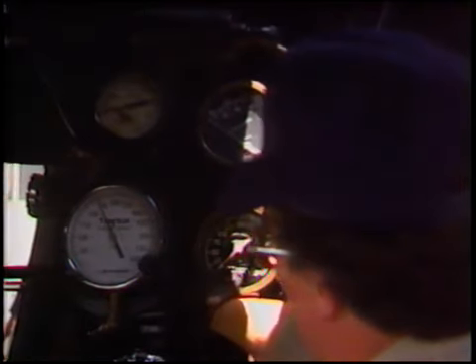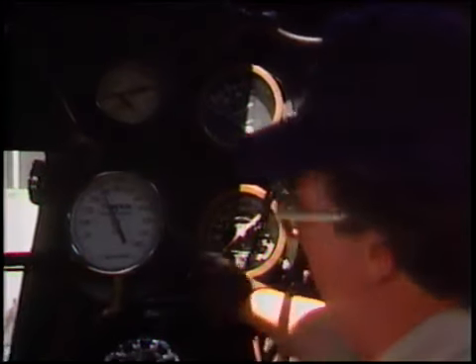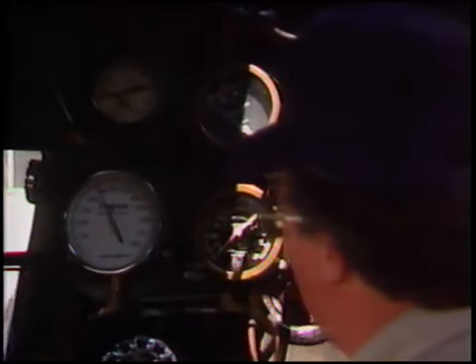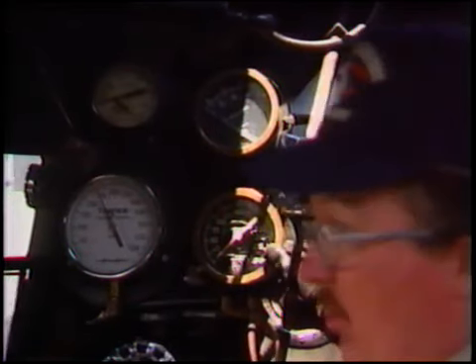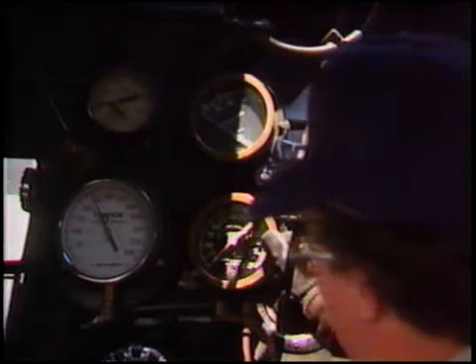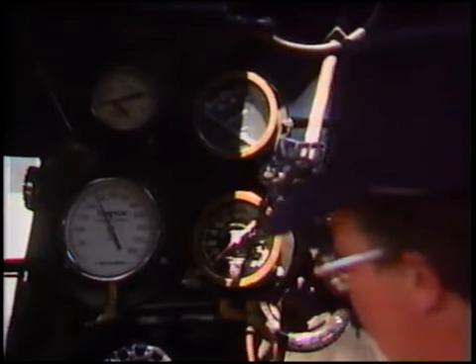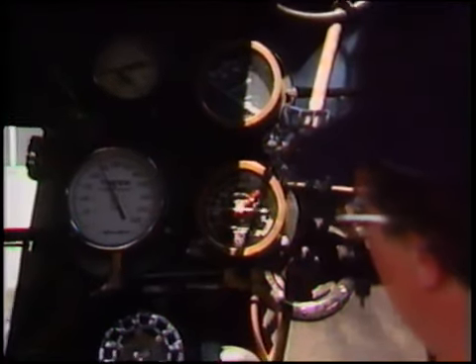The next gauge down to the left is the main steam pressure. 600-pound gauge, 300 pounds once the safety valve goes off that. And to the right here, we have a duplex stoker gauge. It's got two separate needles, one for the blast jets and one for the stoker engine. Once you find your blast jet setting, just leave it there.